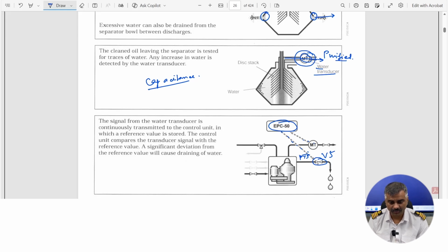So V5 opens by the EPC50 command, and the drain takes place. In further lectures we will explain the time interval for which the drain opens and how many times it opens, when we look at the parameter settings and the parameter list. We will discuss this in more detail then. What the manual says is that the water transducer is continuously transmitting to the control unit, and the reference value is stored. That is also very important. The reference value is stored for how much time it takes for the water alarm to come.